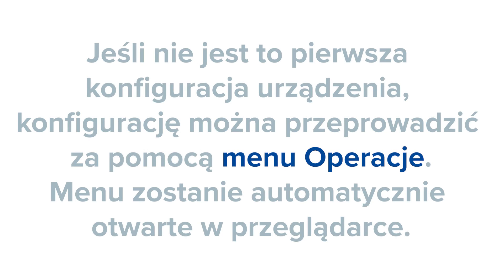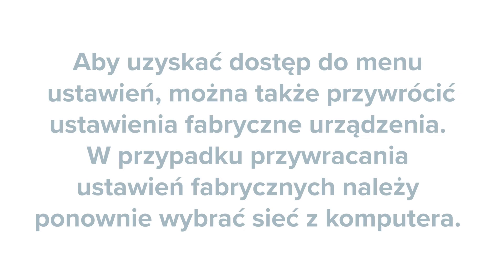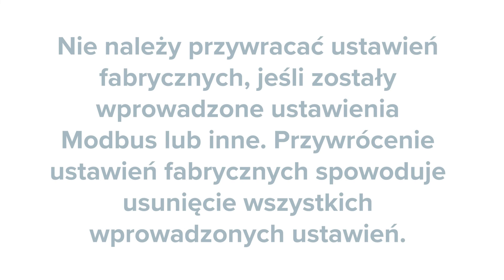If this is not your first setup of a unit, the setup is complete through the operations menu. The menu will open automatically in the browser. You can also restore the factory settings of the unit in order to access the setup menu. If you restore factory settings, reselect the network from the computer. Do not restore factory settings if Modbus or other settings have been made. Restoring factory settings will delete all settings that have been made.